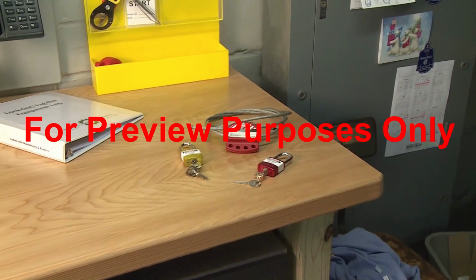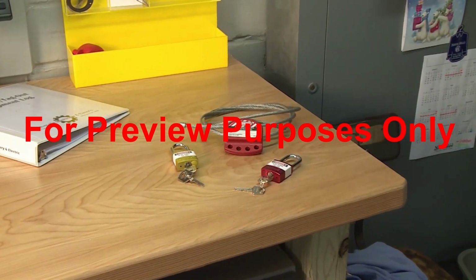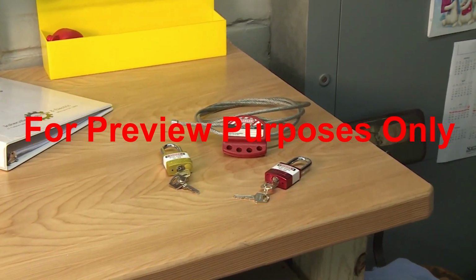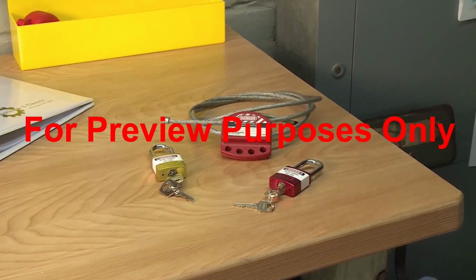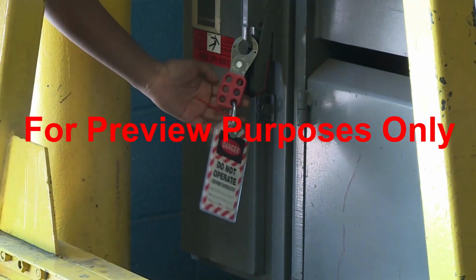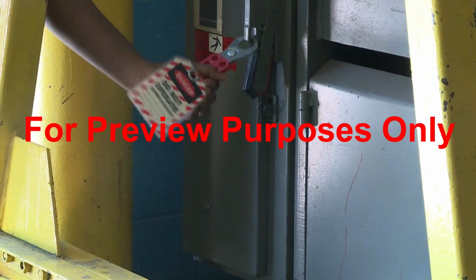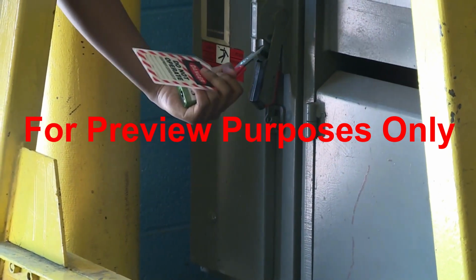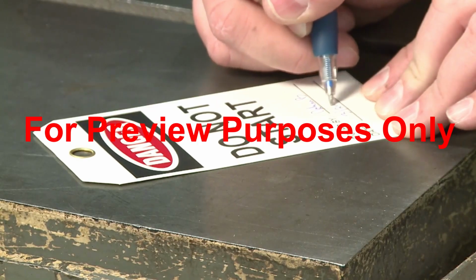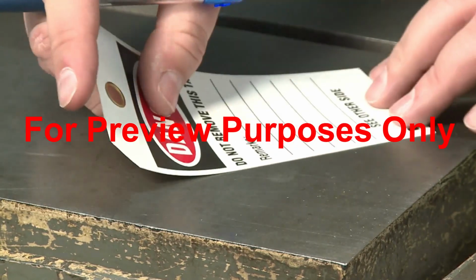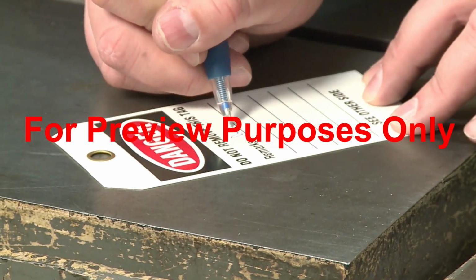To prevent this from happening, lockout-tagout procedures standardize the steps that are followed in the power control process and physically lock a power switch in the off position until energy can be restored safely. A tag is applied to the locked switch, which explains why the power has been shut off and who is doing the work on the equipment.